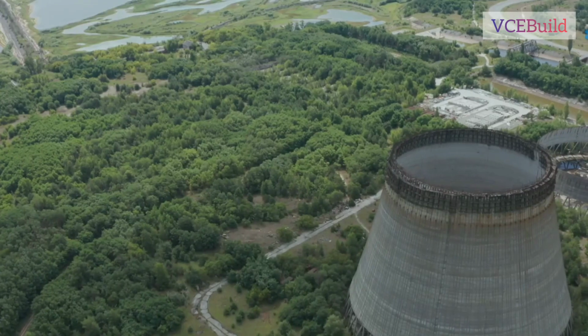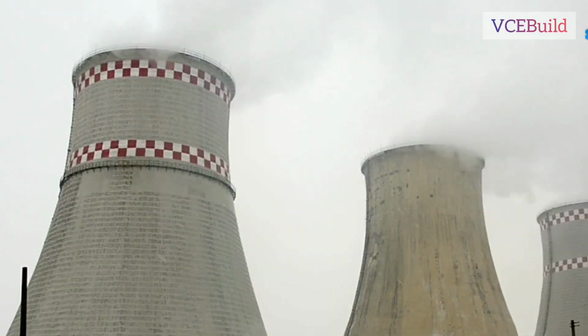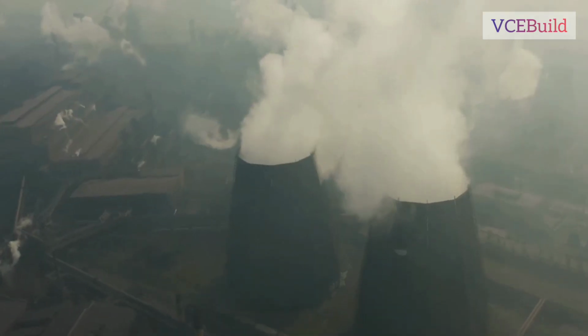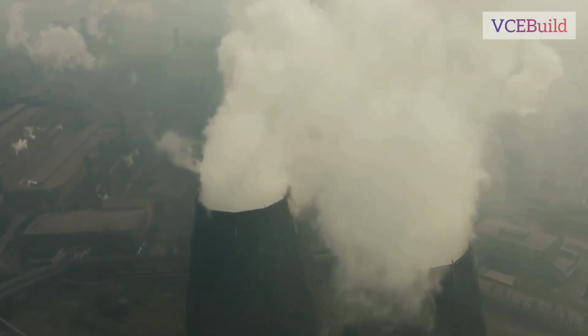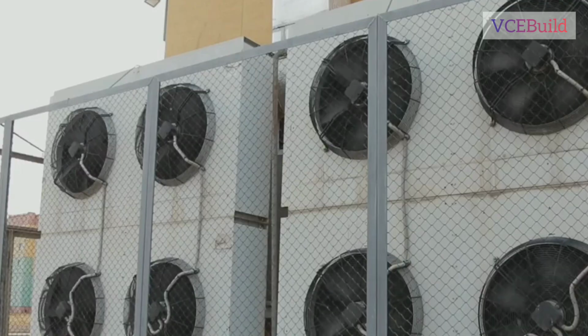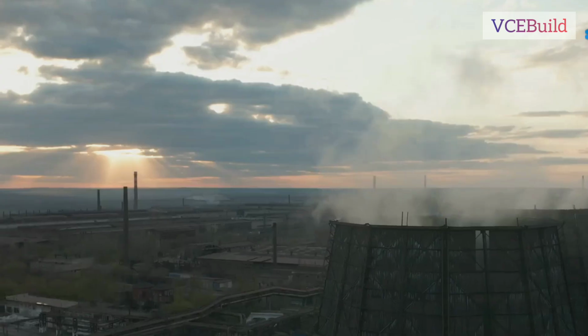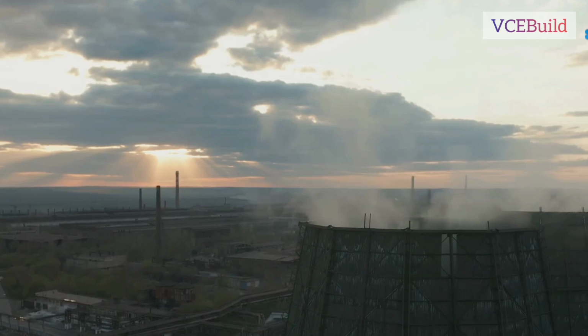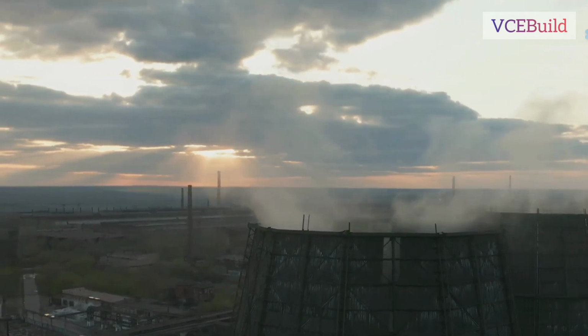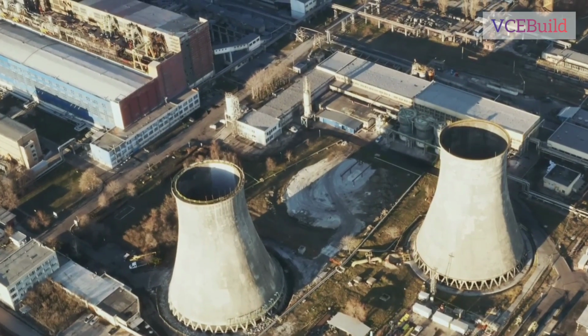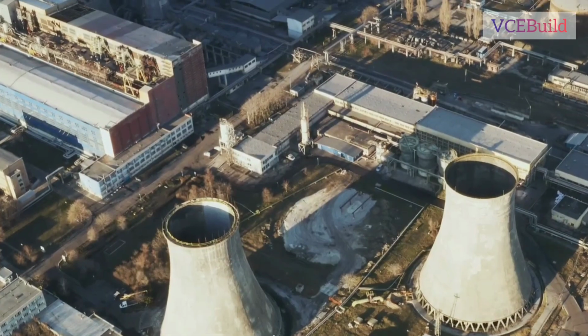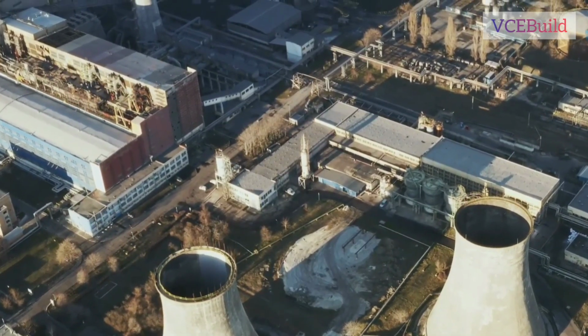Not all cooling towers are created equal. The ones you're probably familiar with, those giant hyperboloid structures, are called natural draft cooling towers. They rely entirely on natural airflow to do the cooling. But there are also mechanical draft towers, which use large fans to force air through the system. These are common in smaller industrial setups, or in places where natural airflow isn't enough. Some even use closed-circuit designs where water flows through pipes instead of mixing directly with air, perfect for areas where water conservation is critical.